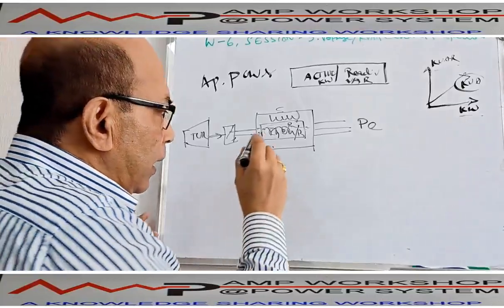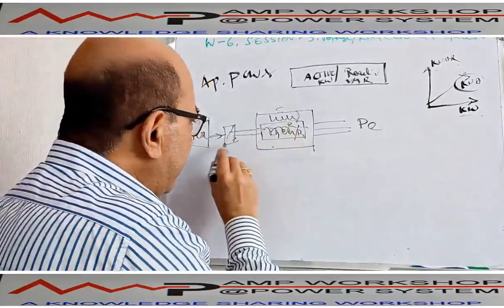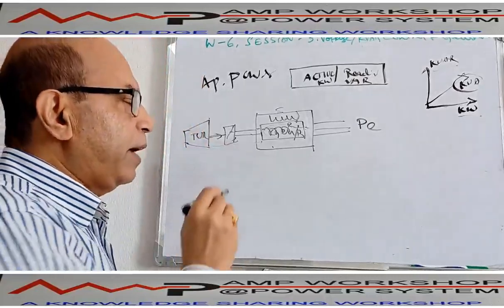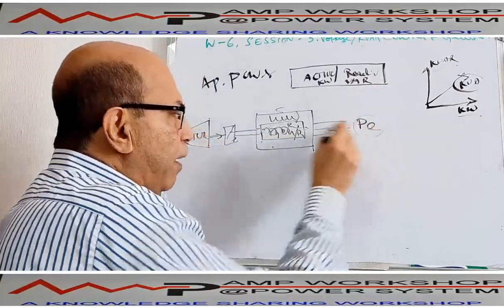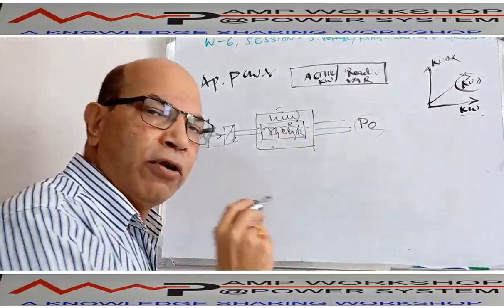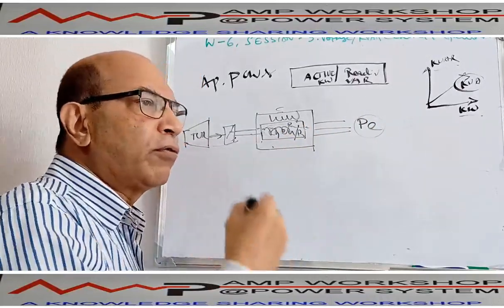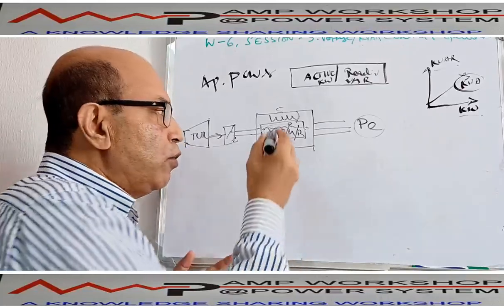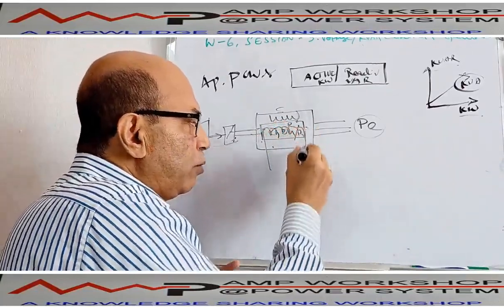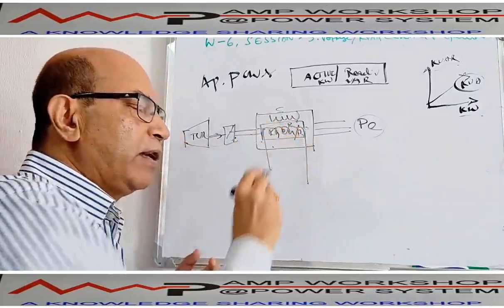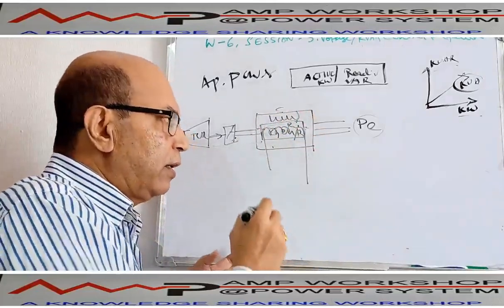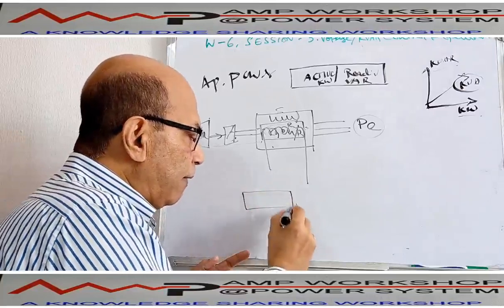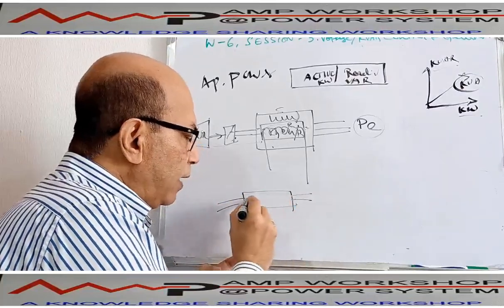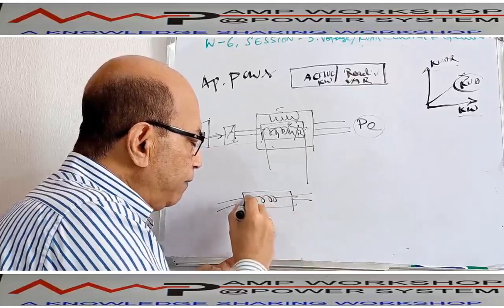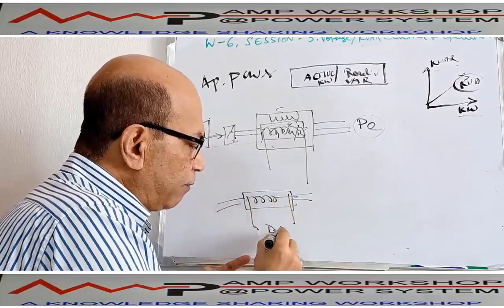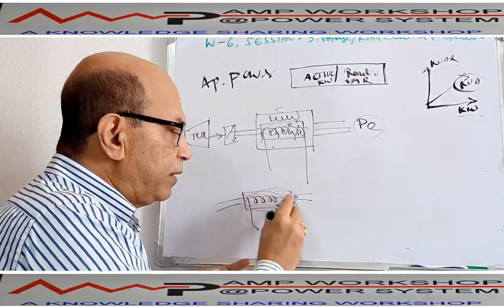Now, when this rotor is rotating, the mechanical power is given by the turbine. But if we want to get electric power only by rotating with the turbine, it will not produce electric power. The rotor is rotating, but it is not producing any power. To produce power, this rotor needs to be magnetized. Suppose this is a cylinder coupled with a turbine shaft, and inside the rotor there is a winding. If this winding gets DC current from some source, then it will be magnetized. I mean, this is a magnet.